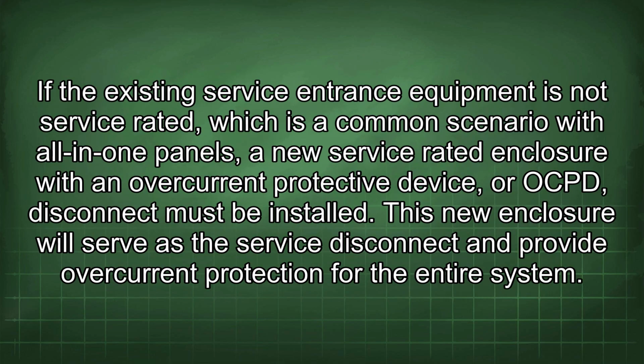If the existing service entrance equipment is not service-rated, which is a common scenario with all-in-one panels, a new service-rated enclosure with an overcurrent protective device, or OCPD, disconnect must be installed. This new enclosure will serve as the service disconnect and provide overcurrent protection for the entire system.